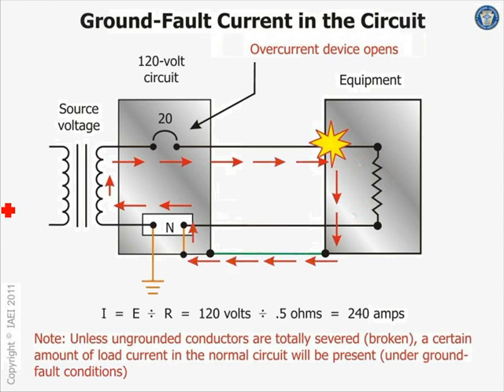The minute that you short, accidentally or intentionally, like Chad likes to play with it, you can go grab phase A or whatever hot one, make hot one touch the equipment, you bypass that impedance, and the current will go right through the equipment. The easiest path would be through the equipment ground conductor all the way. Right here, it jumps over the neutral. Can you see it? Free jump over the neutral back to the source. Now, since the impedance of this path is very low, 0.5, look how much current out of this circuit breaker is going to come up. Very high amount of current. This guy will wake up and trip.